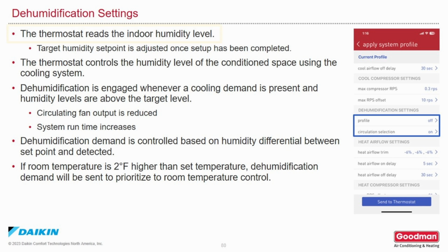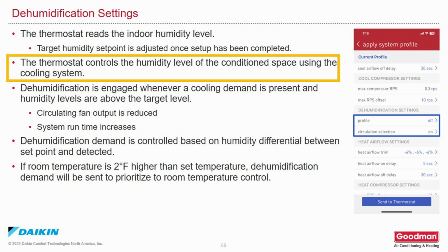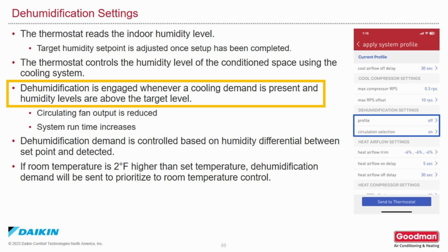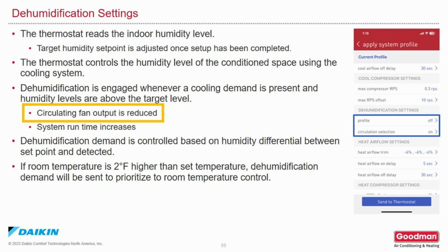Dehumidification settings. The thermostat reads the indoor humidity level. Target humidity set point is adjusted once setup has been completed. The thermostat controls the humidity level of the conditioned space using the cooling system. Dehumidification is engaged whenever a cooling demand is present and humidity levels are above the target level. Circulating fan output is reduced, system runtime is increased.